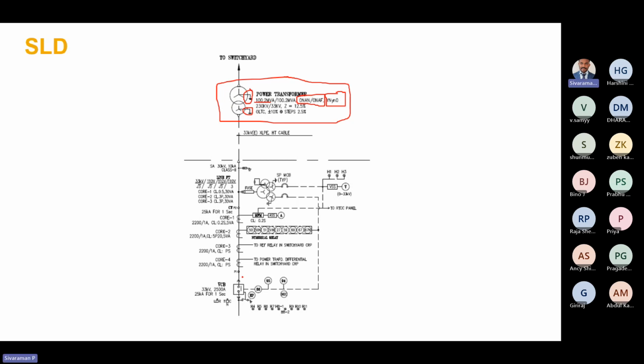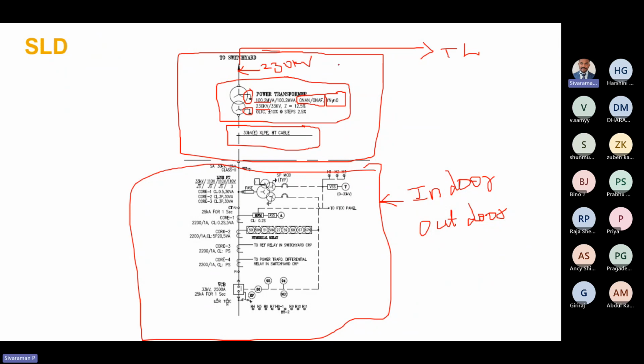For the outgoing feeder of the switchgear to the transformer, 33 kV medium voltage cable is used to connect. Okay, so this will be inside the substation yard area, in most cases. These switchgears will mostly be indoor. In some locations it can be outdoor also. For both indoor and outdoor, there are some additional or different requirements. Okay, so from this 230 kV side, at the 230 kV voltage level, there will be a transmission line that will connect to the existing substation.